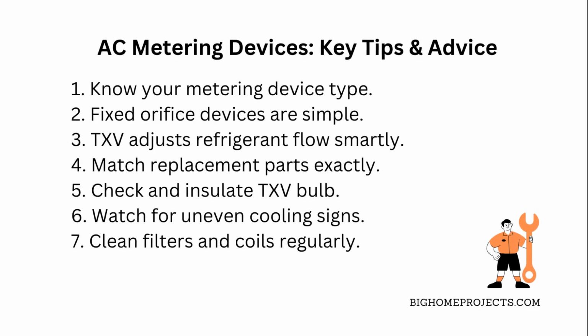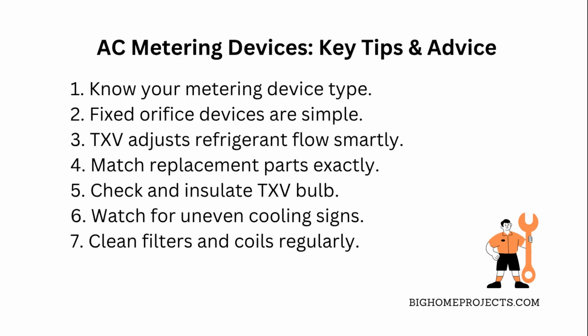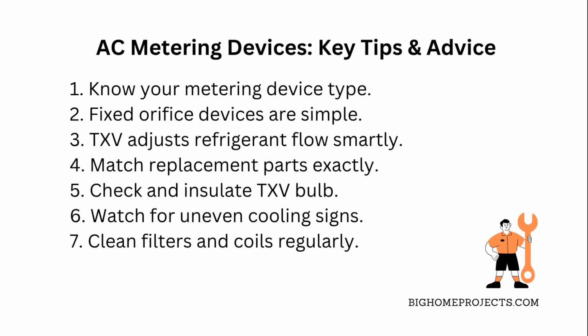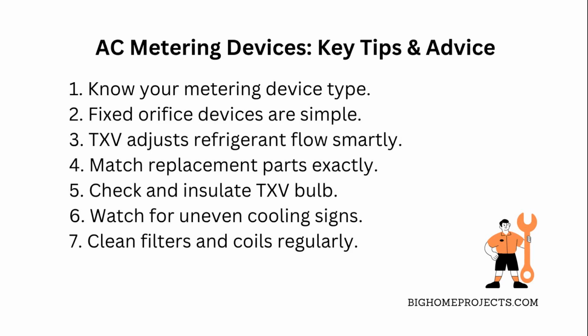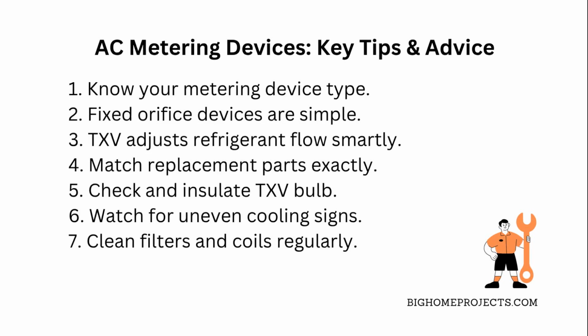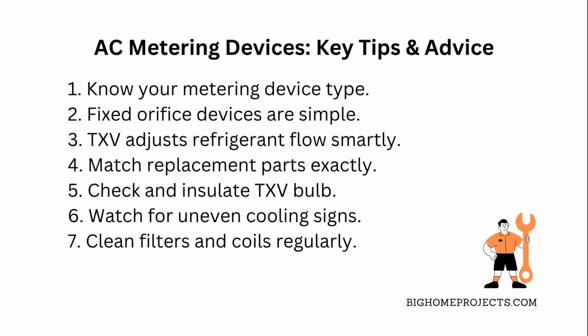You want to remember that these are super cost effective, but they don't adjust for changing temperatures or pressures, so they can be kinda limited. Then there's the thermostatic expansion valve, or TXV, which is way smarter because it adjusts the refrigerant flow based on the cooling load. This means your AC stays more efficient and cools better during those hot days.